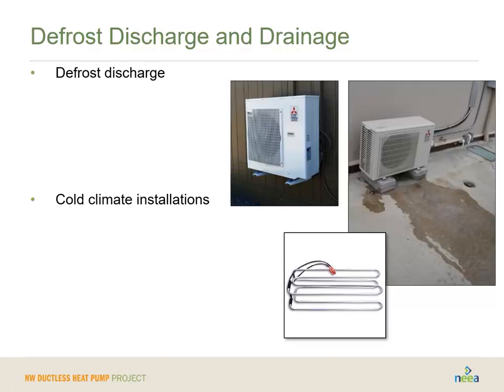Defrost discharge, another challenge. During the defrost cycle, any frost that's built up on the outdoor coil will usually be defrosted because the system goes through a special cycle where it reverses temporarily. So during cooling mode, it temporarily provides a little heat or reverse. It will defrost any frost that's on the coils, but it will also create some moisture that comes off it. So being smart about where you install your outdoor compressor and making sure your discharge drains appropriately is really a good idea.